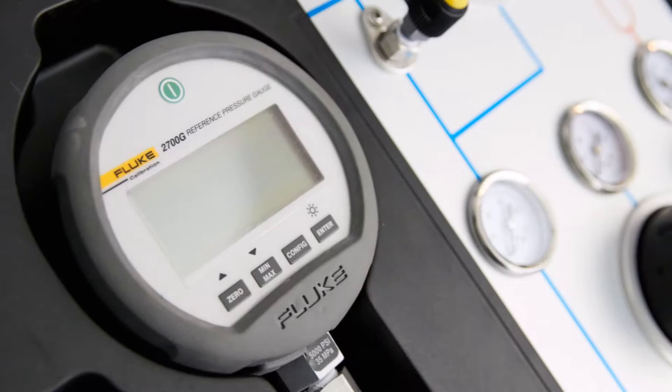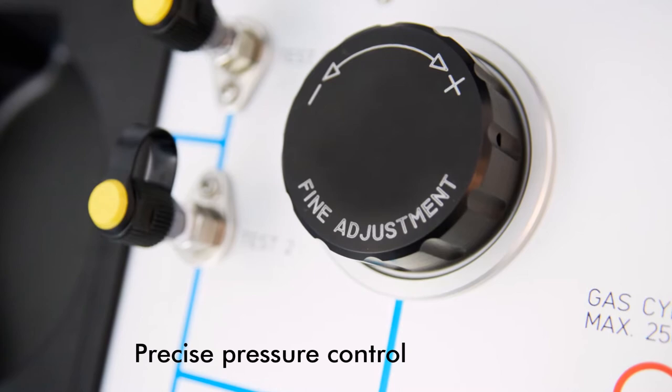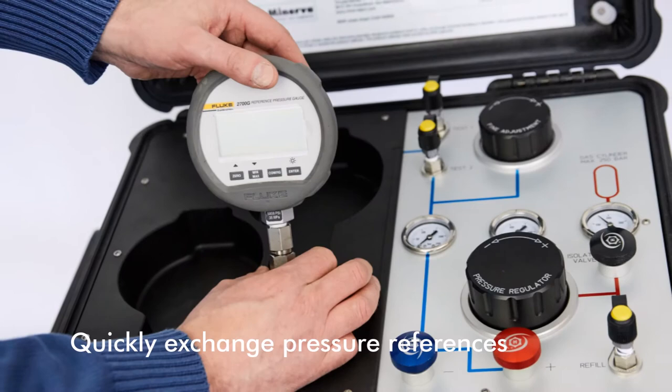This enables you to perform safe pneumatic calibrations up to a maximum pressure of 250 bar, not contaminate the device on test with oil or water, perform precise test pressure control using a pressure balanced volume adjuster, eliminate trouble with trapped air in a hydraulic system, and exchange pressure references quick and easy.